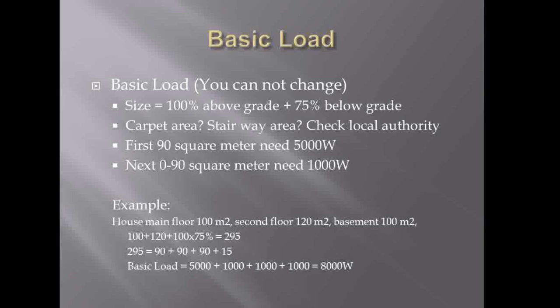Once you have the size of your property, according to the Canadian Electrical Code, you need 5,000 watts for the first 90 square meters of basic load, then an additional 1,000 watts per 90 square meters after that. For example, if your main floor is 100 m², second floor is 120 m², and basement is 100 m², the total area is 100 + 120 + 75% of 100 = 295 m². Breaking that down: 295 = 90 + 90 + 90 + 15. The first 90 needs 5,000W, the next two 90s need 1,000W each, and even the last 15 m² needs another 1,000W, giving you a total of 8,000 watts.